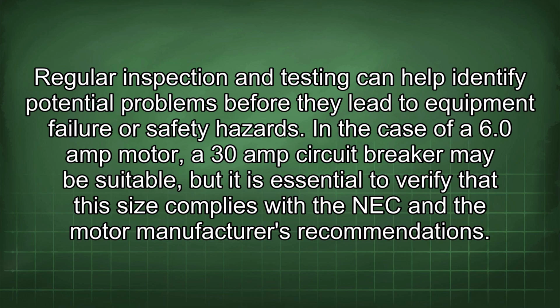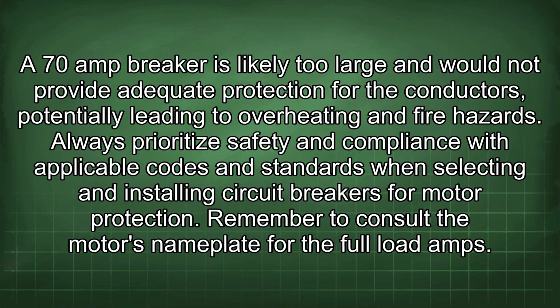In the case of a 6.0 amp motor, a 30 amp circuit breaker may be suitable, but it is essential to verify that the size complies with the NEC and the motor manufacturer's recommendations. A 70 amp breaker is likely too large and would not provide adequate protection for the conductors, potentially leading to overheating and fire hazards. Always prioritize safety and compliance with applicable codes and standards when selecting and installing circuit breakers for motor protection. Remember to consult the motor's nameplate for the full load amps.